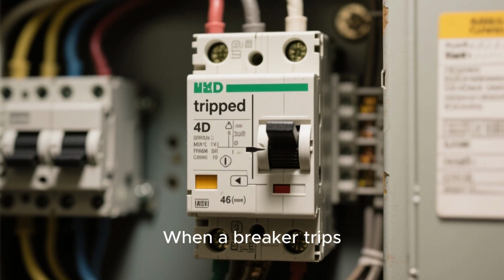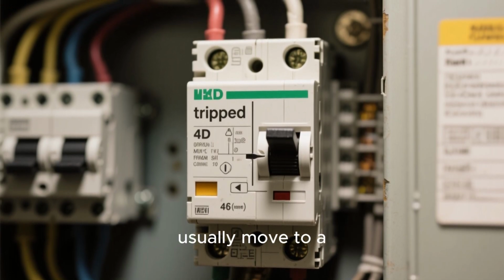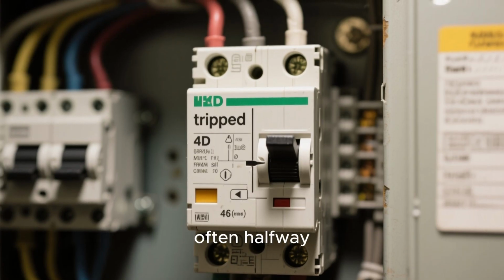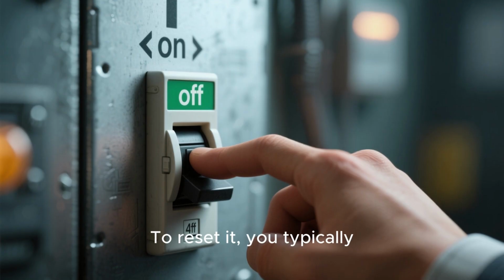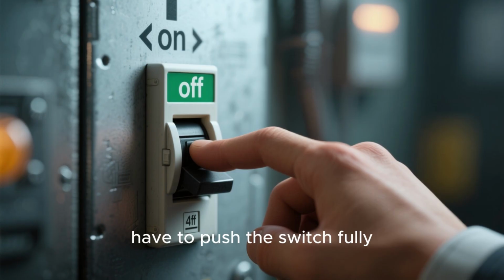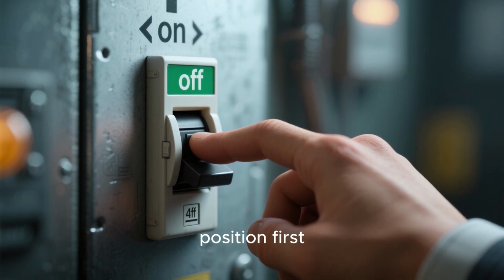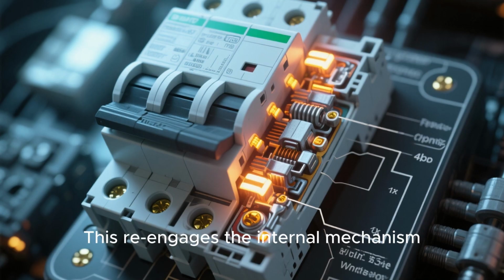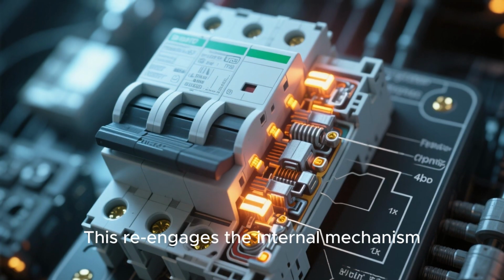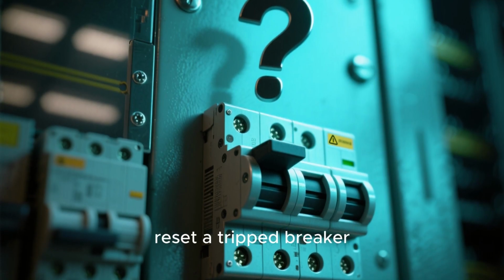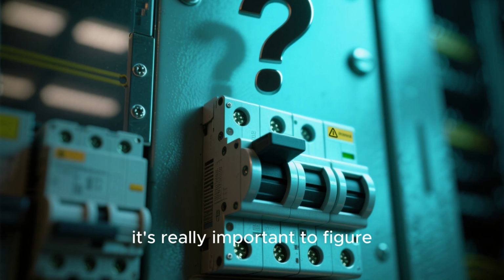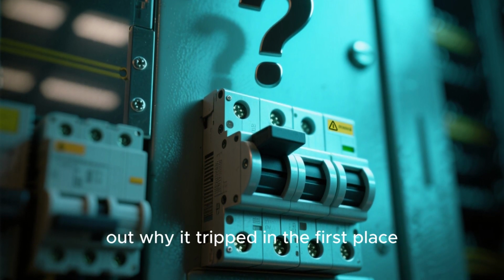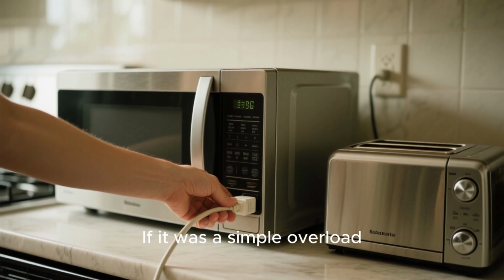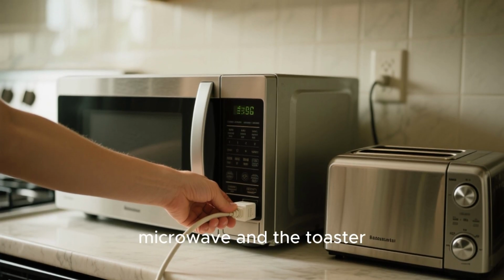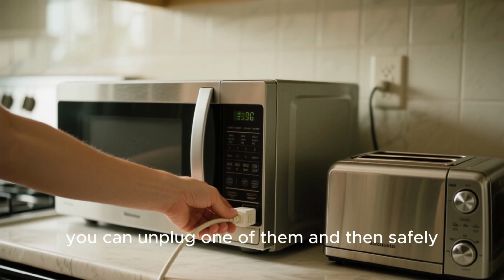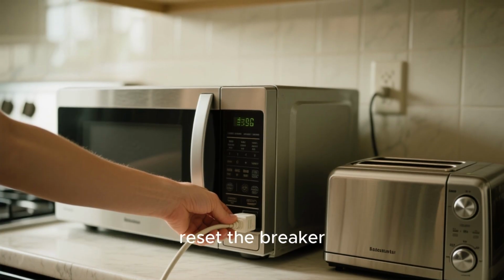When a breaker trips, the switch on the front will usually move to a tripped position, often halfway between on and off. To reset it, you typically have to push the switch fully to the off position first, and then back to on. This re-engages the internal mechanism. Now, before you go and reset a tripped breaker, it's really important to figure out why it tripped in the first place. If it was a simple overload because you ran the microwave and the toaster at the same time, you can unplug one of them and then safely reset the breaker.